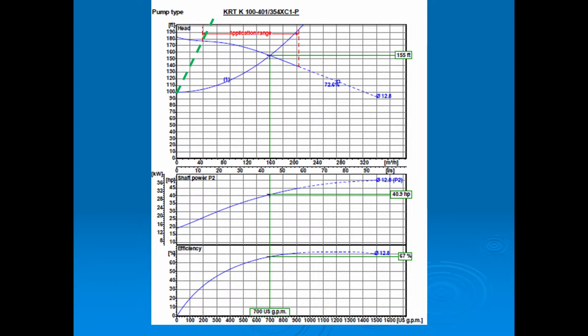The reason is that the friction in that pipe is a representation of friction. The faster we pump water through that pipe, the more friction we have, just like driving your car down the highway. The faster you drive, the more friction you have. Therefore, it takes more energy to get there. Same thing here. In our business, we have a saying: you can only pump so much poop through the pipe. So that friction is going to go up, not in a straight line but in a parabola, based on the velocity of water through that pipe.